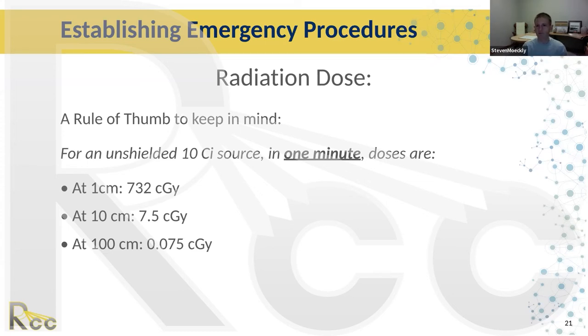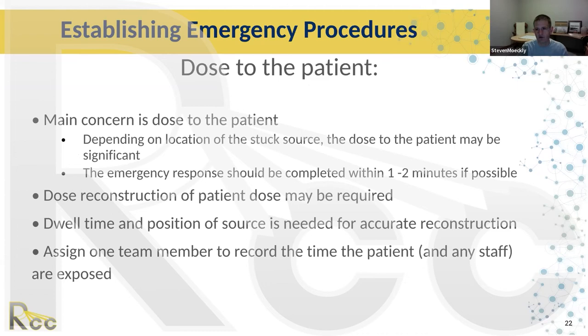When initiating these responses, keep your head and think about where the source is and how dangerous the situation is. As a physicist, if the doctor needs a hand I can assist; if not, I can step back to one meter and be very safe while still being available. Your main concern is dose to the patient. Emergency response should be completed in one to two minutes. Dose reconstruction of the patient may be required — time and position of the source are needed for accurate reconstruction.